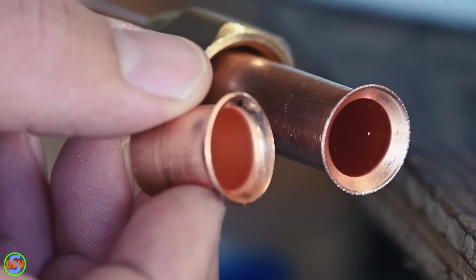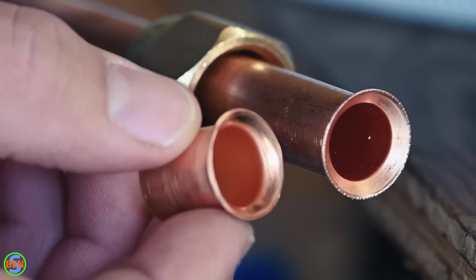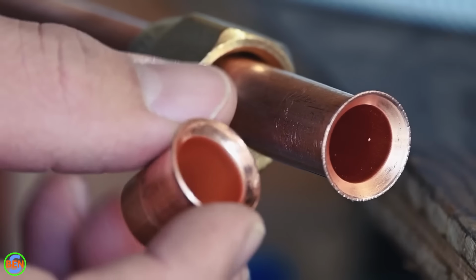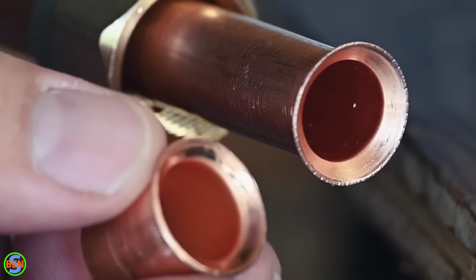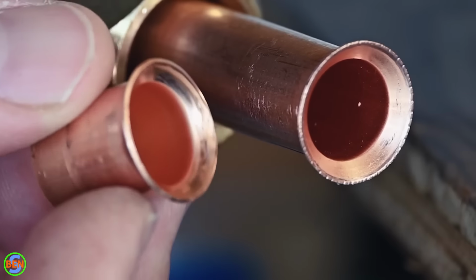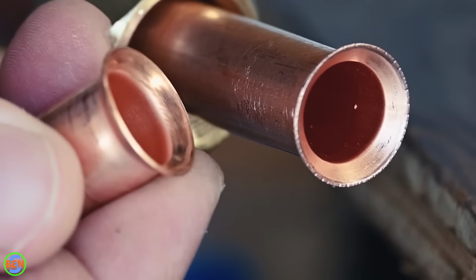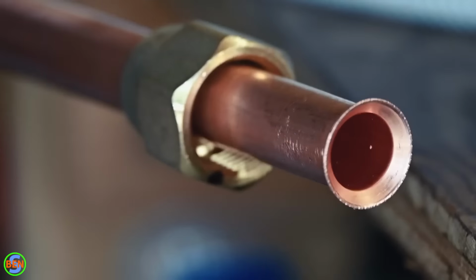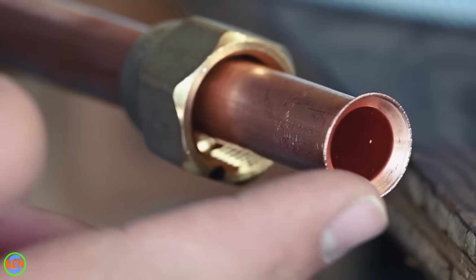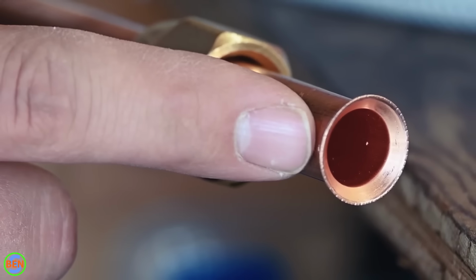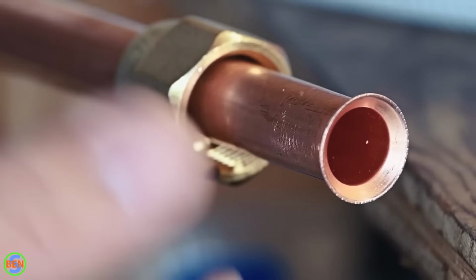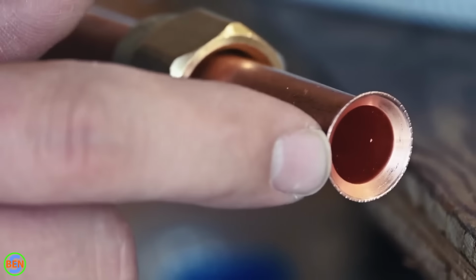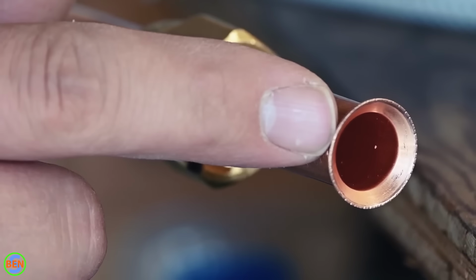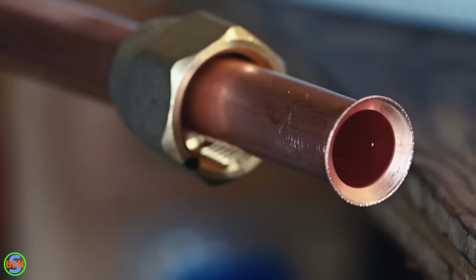Here's the difference between the factory flare that I'm holding in my hand here and the flare that we just created. You can see that there are a few more imperfections in the face of the factory flare than we have in the flare that we just created. And you can see what I'm talking about with that burr. By reaming this with the needle nose a little bit, it pushes that burr out enough that when you flare it, that burr stays to the very outer edge and it doesn't get rolled over onto the inside.